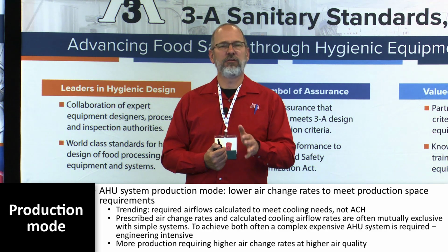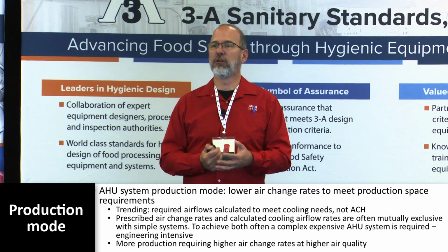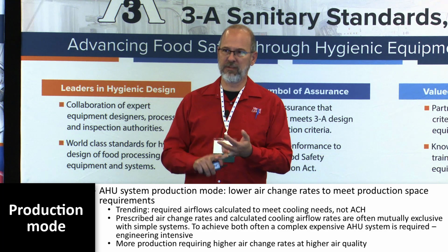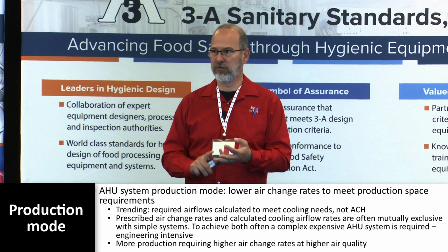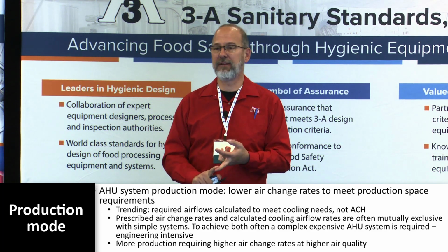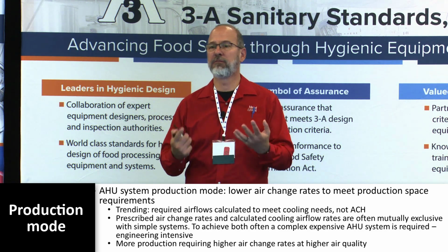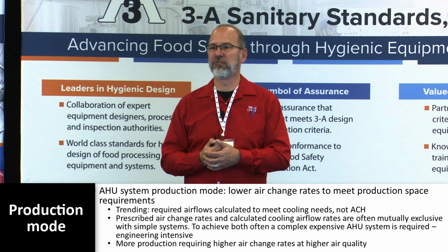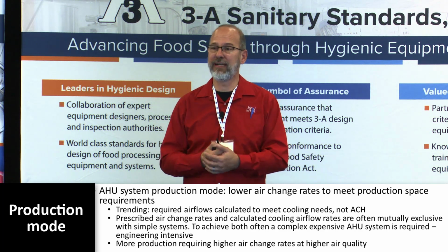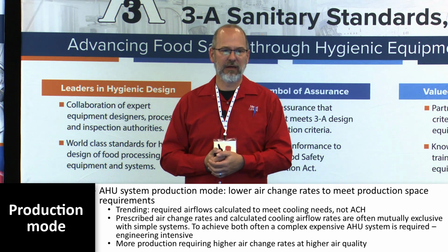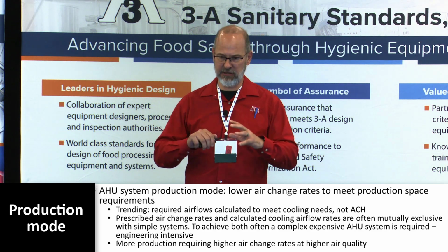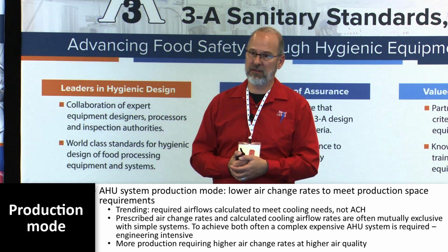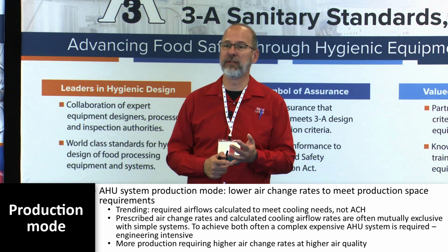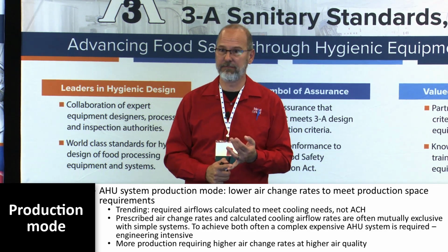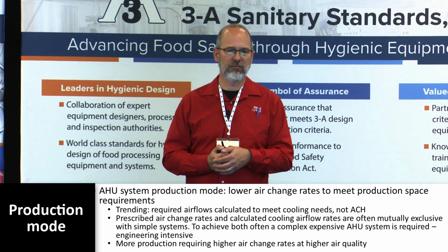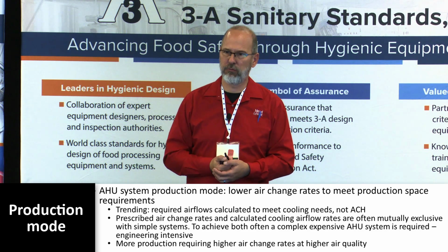Typically those units are sized based on all the loads in the room: the number of occupants in the room, the heat gain in the room from process equipment, motors, heat exchangers, the heat gain from lights, heat gain from building envelope, and a lot of other sources. Those all add to the heat gain or moisture gain in the room. So we've got to get rid of all that. Once those things are identified, an HVAC engineer can just do calculations, figure out how much heat gain and moisture gain that is, and size a unit, and size the airflow for the unit to get rid of it. That will result in an air change rate for that room.